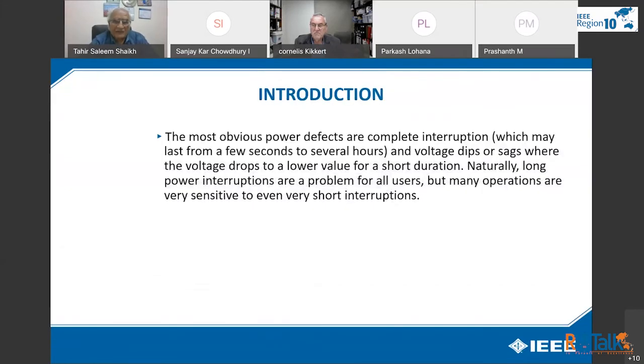The most obvious power defects are complete interruption, blackout, which may last for a few seconds to several hours, and voltage dips or sags, where the voltage drops to a lower value for a short duration. Naturally, long power interruptions are a problem for all users, but many operations are very sensitive to even very short interruption like dips or sags.